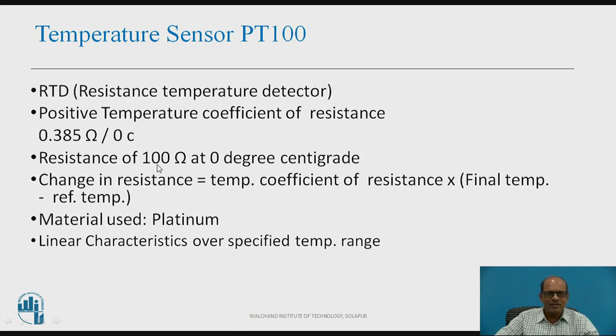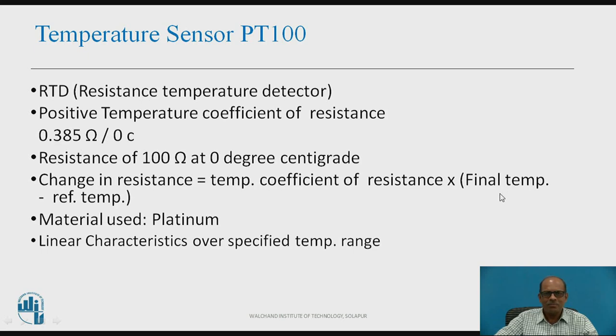The resistance of PT100 at 0 degree centigrade is 100 ohm and its resistance at 100 degree centigrade is 138.5 ohm. Using this temperature coefficient of resistance, we can calculate the change in resistance due to change in temperature. The formula is: change in resistance equals 0.385 ohms per degree centigrade multiplied by (final temperature minus reference temperature). The characteristics of PT100 are linear over the specified temperature range.